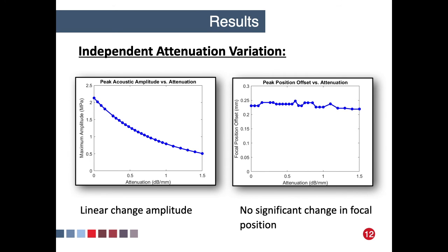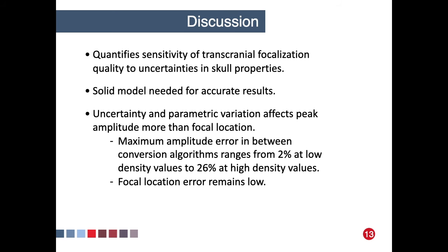of the transducer. And so to summarize the contributions of this work, we quantified the sensitivity of transcranial focusing to the existing uncertainty in derived skull properties based on a homogeneous ray tracing model. We did find that a solid model of the skull, which includes shear waves, was necessary to obtain accurate results, and we demonstrated how the parametric variation created more significant error in the maximum acoustic amplitude at the focus compared to the error in positioning.